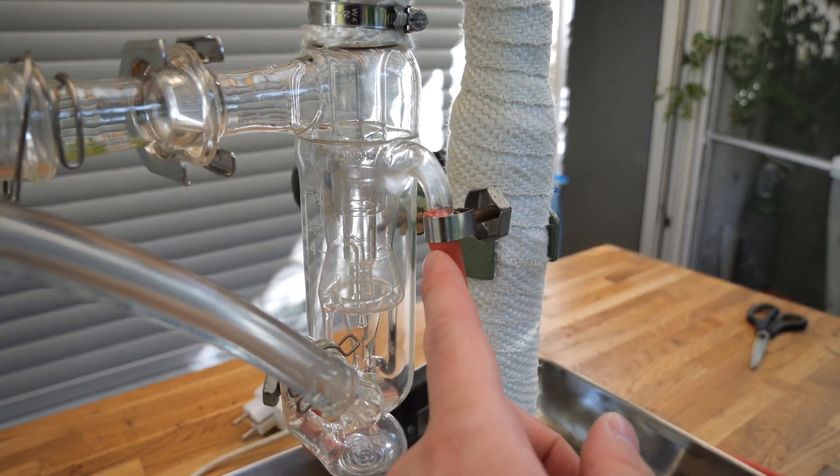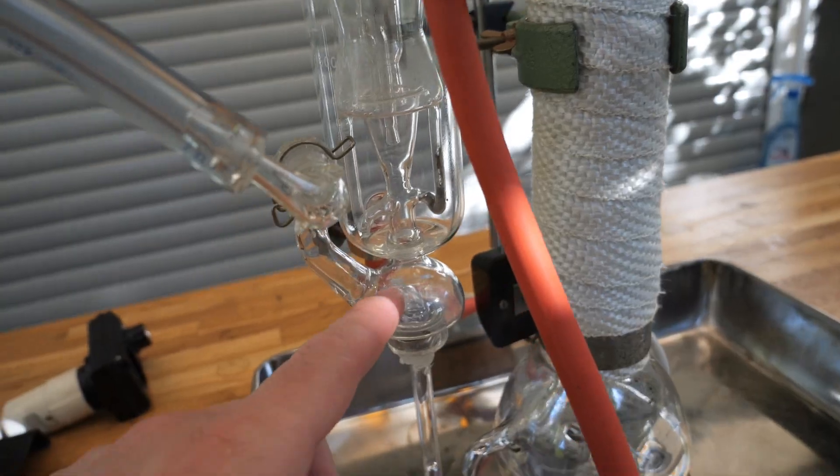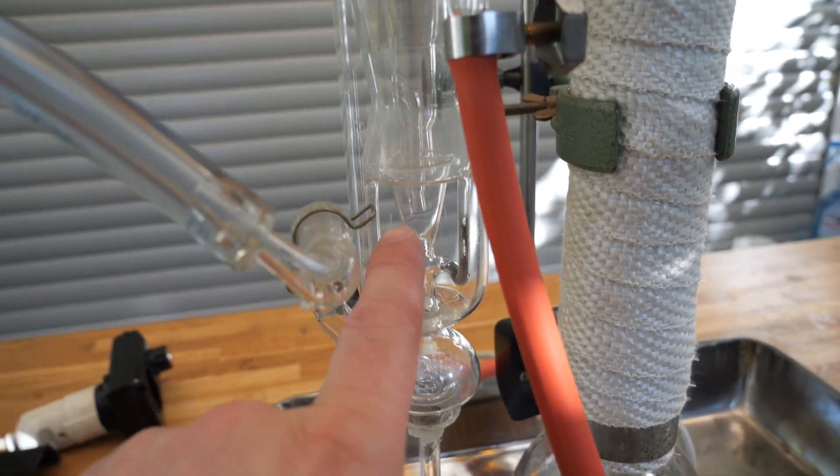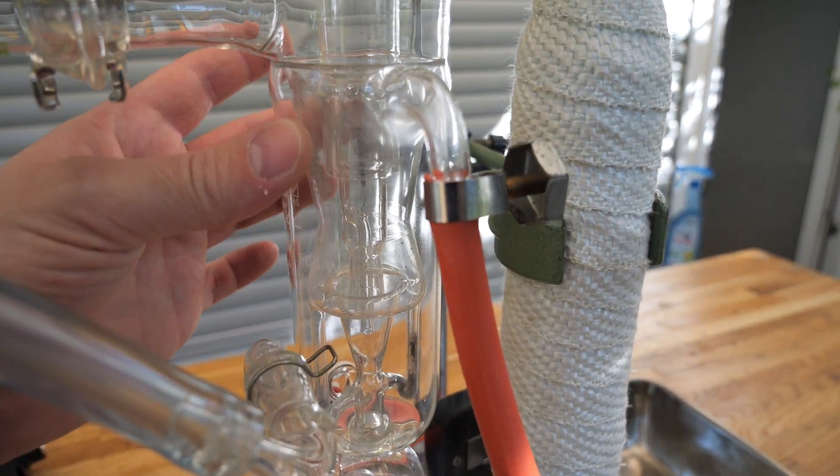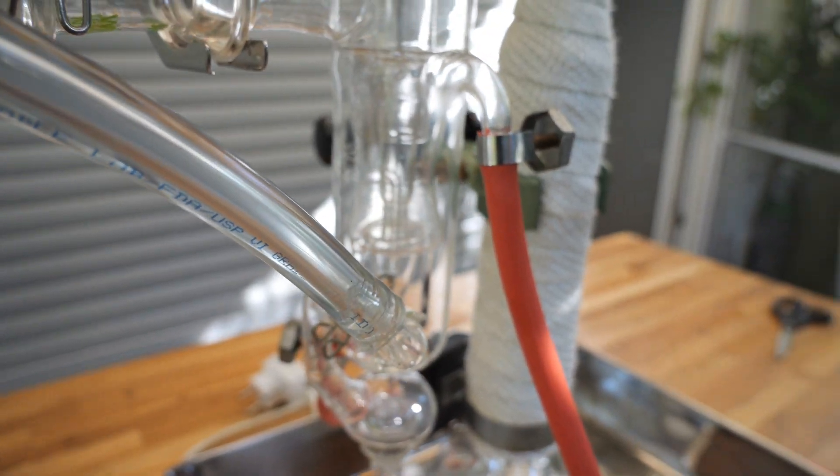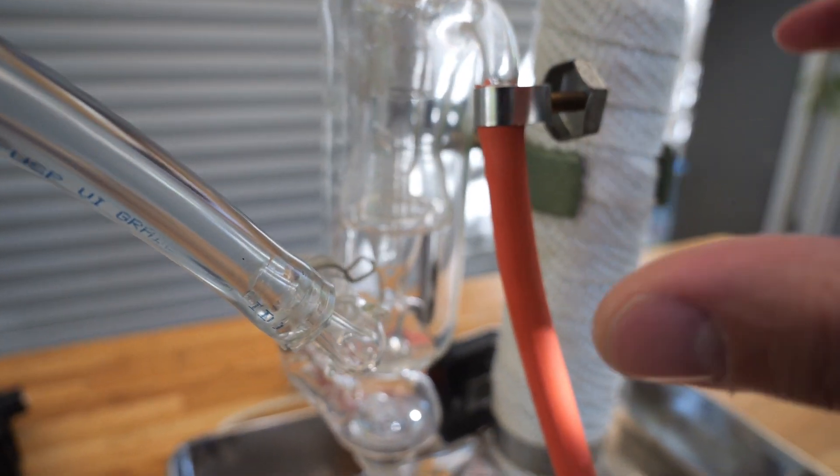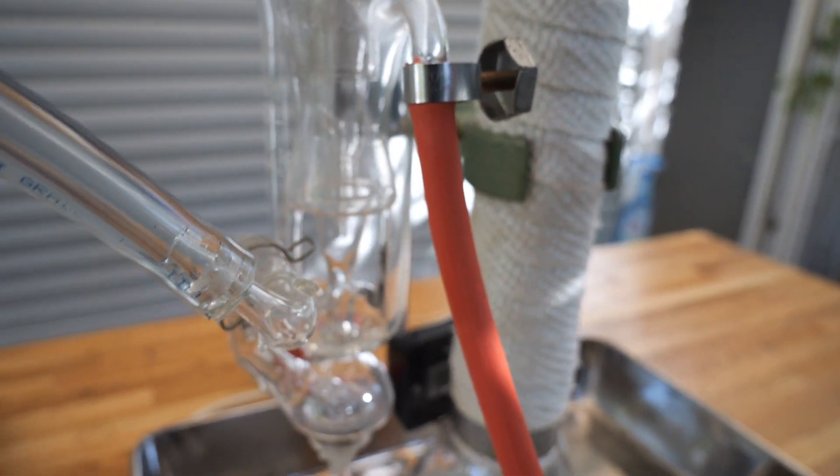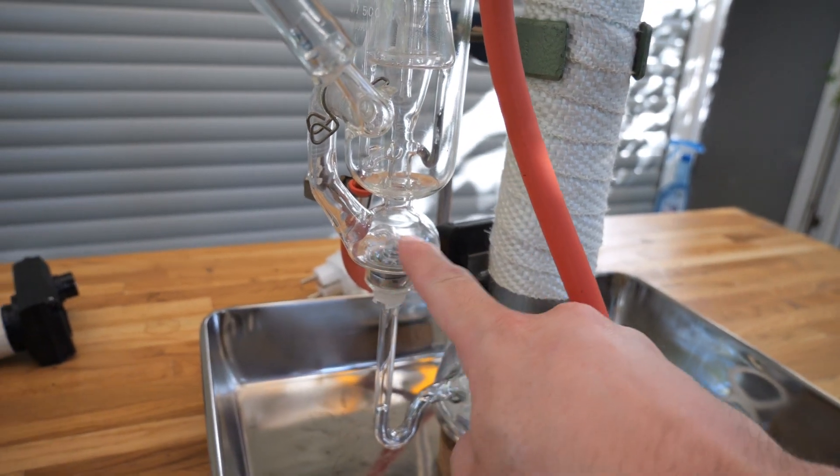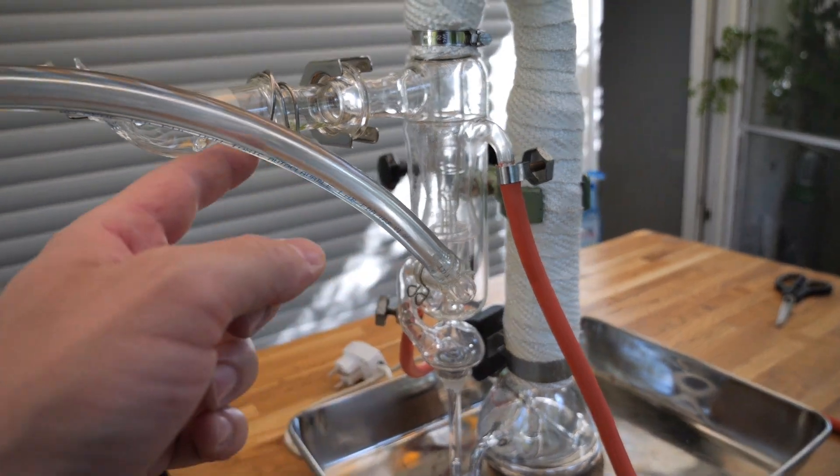There are basically four connections at this diffusion pump. Two of them are for the cooling water which is the one on top here and at the bottom here. The cooling water is flowing through this outer jacket here and cools the mercury vapor which is condensing. Just as a quick reminder the mercury vapor basically transfers its impulse to the gas particles in the vacuum.